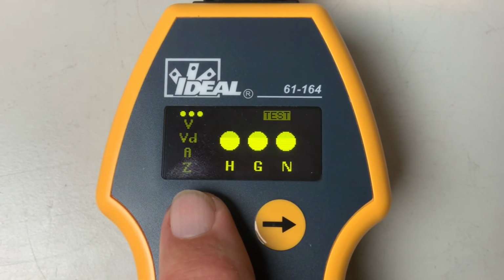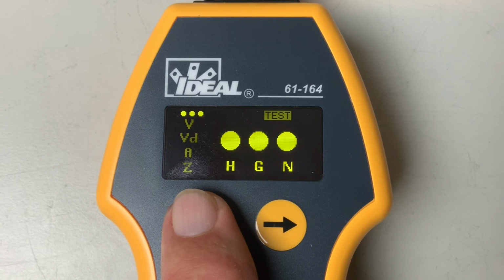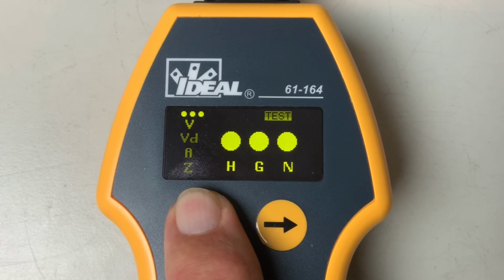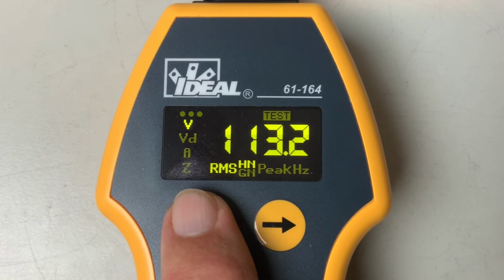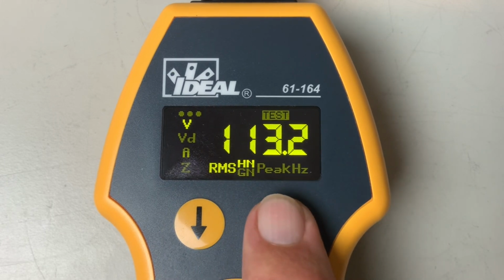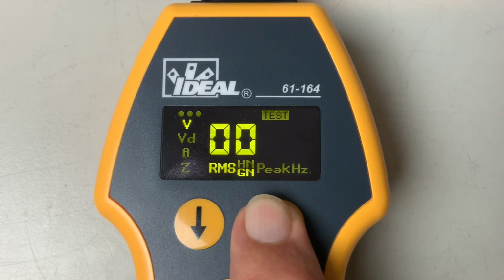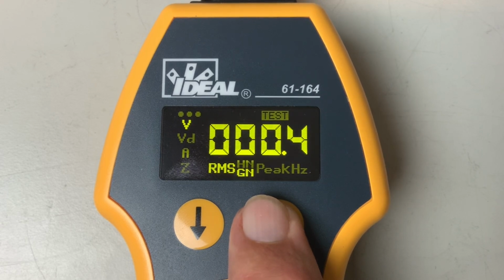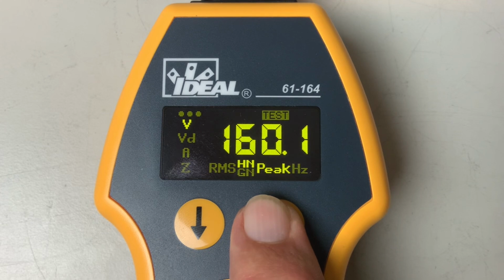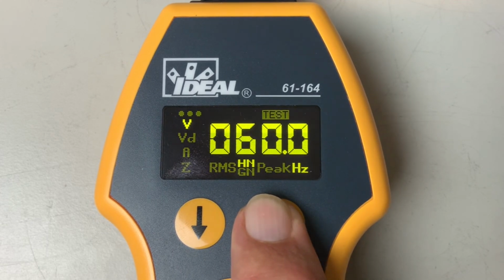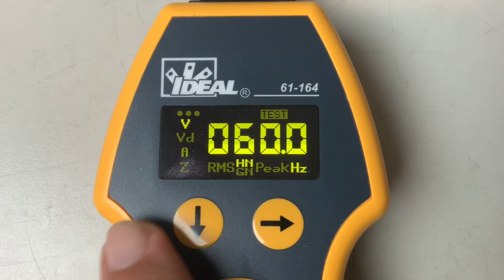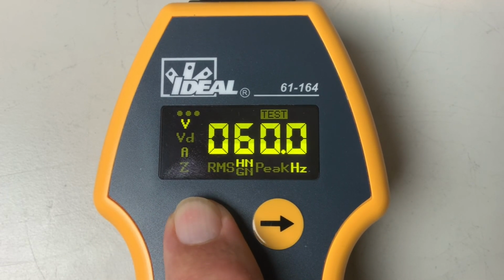From the wiring screen, you have 4 other screens you can go to. The first one is the current voltage measured on the line. The first measurement you see is your hot to neutral voltage or your regular outlet voltage. Then you can go ground to neutral, which will help you identify issues with your ground or your neutral wire, and we'll cover that in more detail. Peak is a useless voltage. It's your RMS voltage times 1.414. It's just a calculated value. And then Hertz is also probably useless for most people because it's always going to be 60.